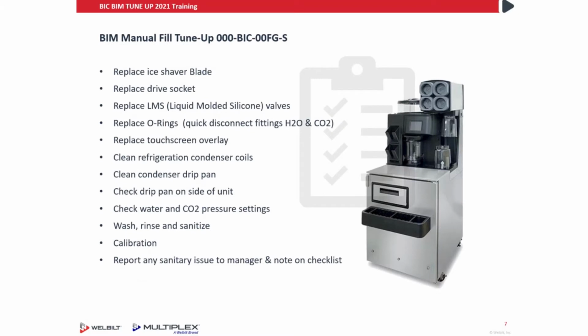Our BIM tune-up will include replacing the ice shaver blade, the drive socket, the LMS valves, the O-rings for the water and CO2 fittings. We're going to replace the touchscreen overlay. We're going to clean the refrigeration condenser coils, the condenser drip pan, the drip pan on the side of the unit, the water and CO2 pressure settings. We're going to check those. We're going to do a wash, rinse, and sanitize.